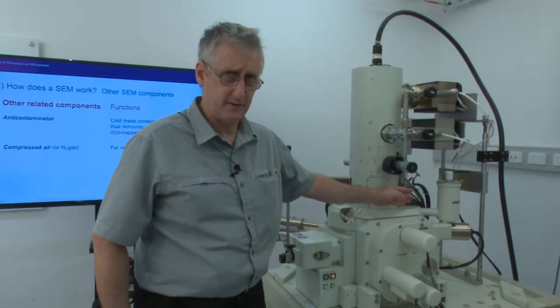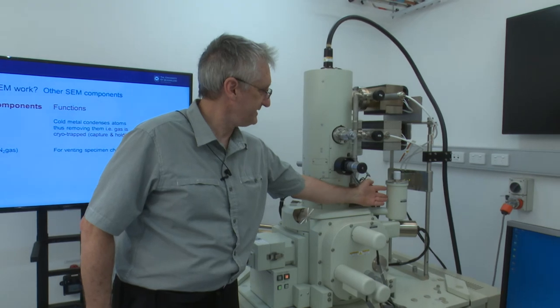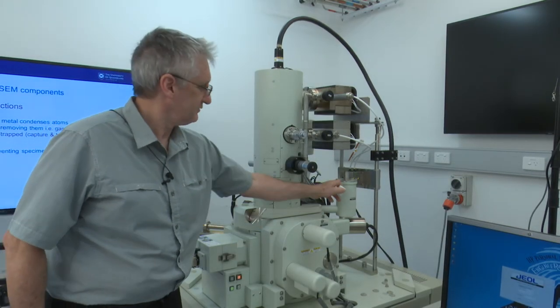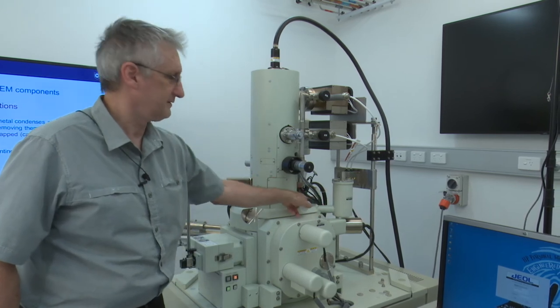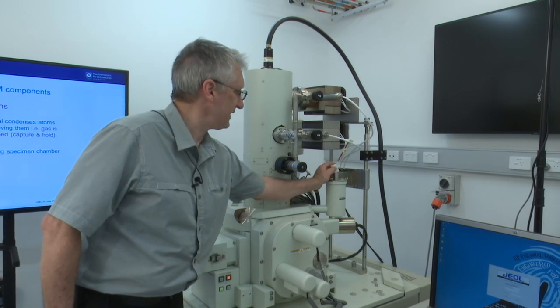So here on the 7100, we have the anti-contaminator dewar that gets filled with liquid nitrogen and cools a copper braid. It goes into a cold point inside the column. It's not always used, but it's there if it's needed.